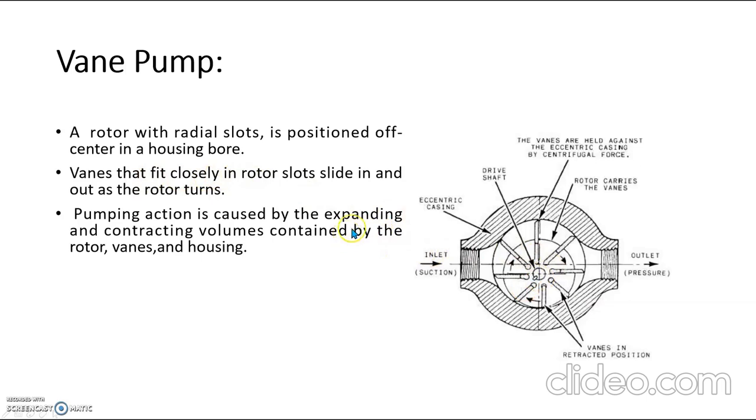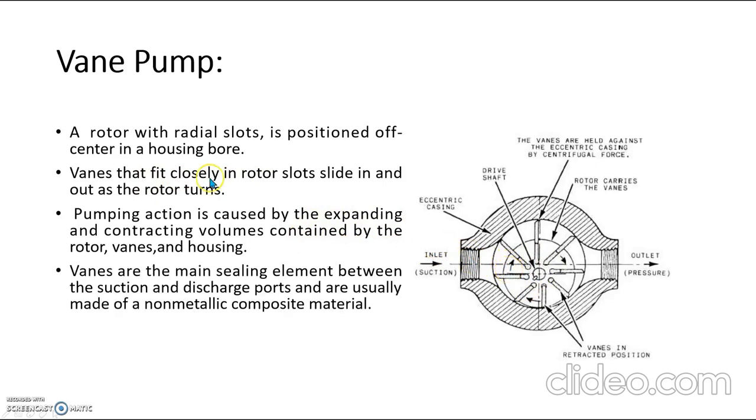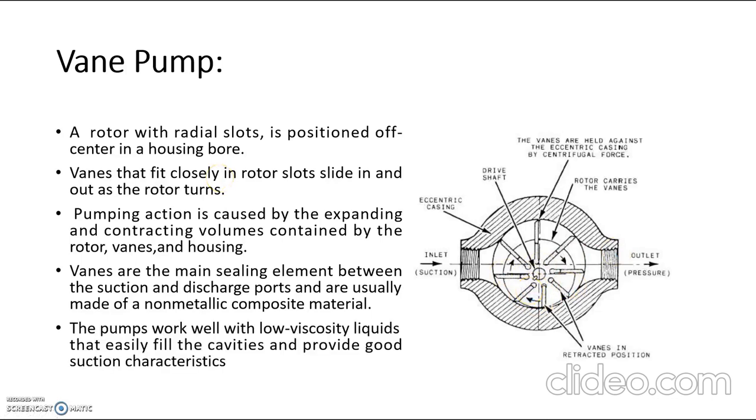This pumping action is caused by the expanding and contracting volumes contained in the rotor, vane, and housing. You can see these sliding vanes, and these sliding vanes act as the main sealing element between the suction and discharge port. These vanes are usually made up of non-metallic composite material. These pumps work well with low viscosity liquids.